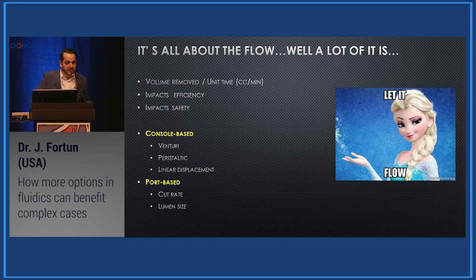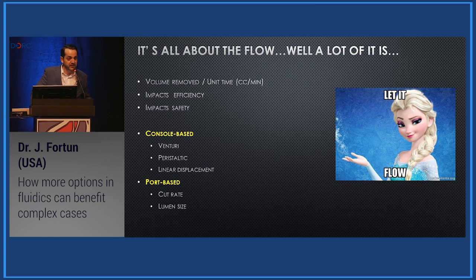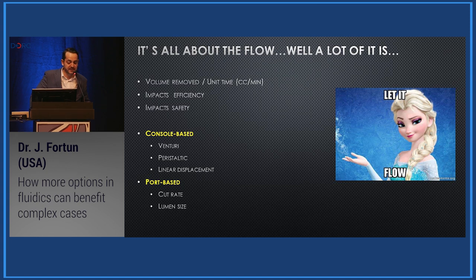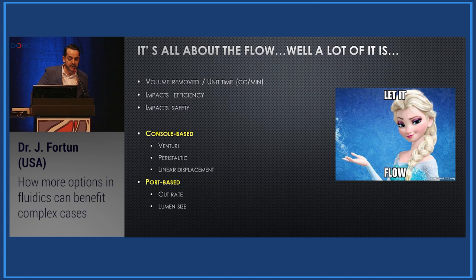Fluidics is kind of complicated, and part of the issue is that you have all these different parameters that at the end of the day really affect two things: flow rates and vitreoretinal traction. We care about those two things because what really matters is not only the ease of our surgery — which is efficiency — but how safe our surgery is. Vitreous flow is defined as the volume removed per unit time, and it can be controlled at the console level or at the port level, a term coined by Steve Charles.